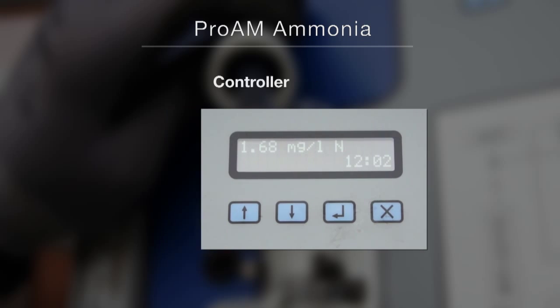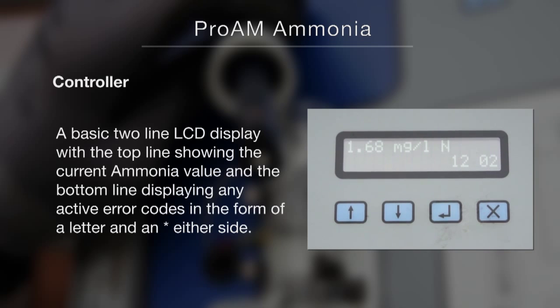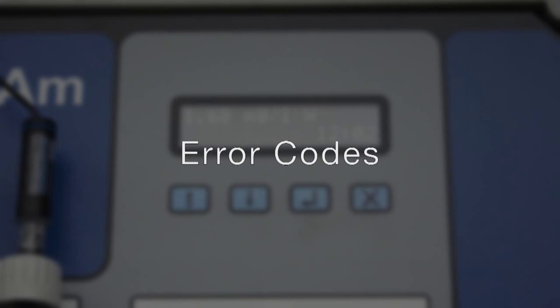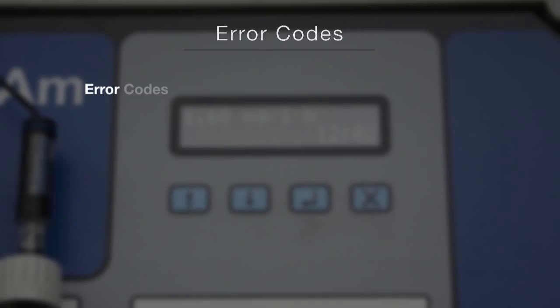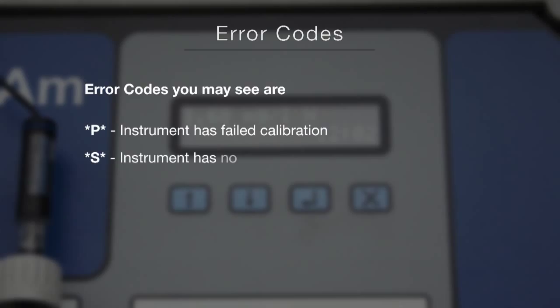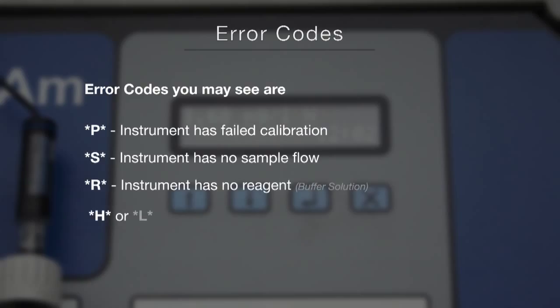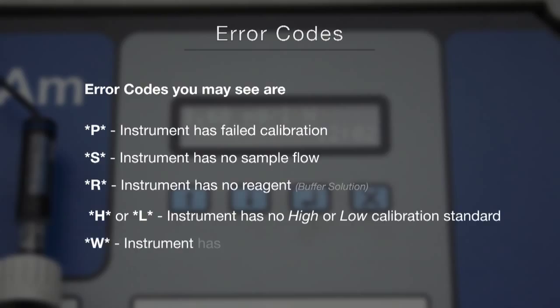The controller is a basic two-line LCD display with the top line showing the current ammonia value and the bottom line displaying any active error codes in the form of a letter and an asterisk either side. The error codes you may see are P, instrument has failed calibration. S, instrument has no sample flow. R, instrument has no reagent. L or H, instrument has no high or low calibration standard. And W, the instrument has no wash solution.